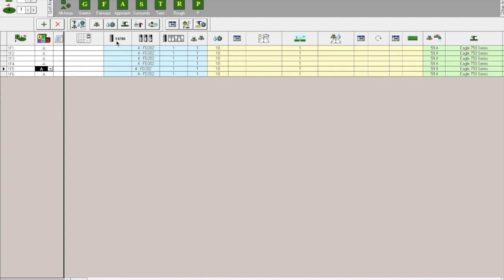As well, in this column right here, this is where you'll want to enter in your decoder address. Each hole and station is going to have a specific number sequence to follow. Numbers cannot be duplicated. So here you can click 1, 2, 3, 4, and if you were to duplicate a number again, you hit enter, it's going to give you an error that says that address is already in use.